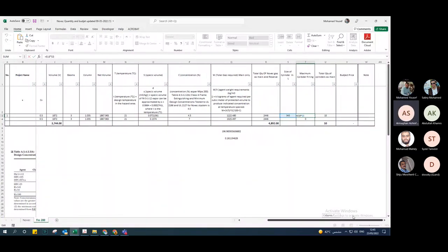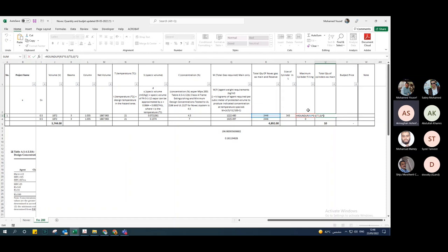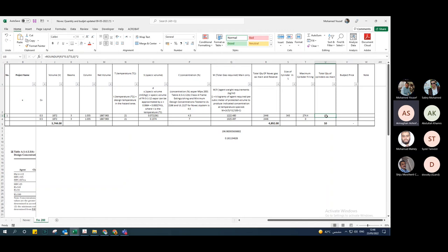I consider the cylinder to be filled to 80% of total capacity. I divide the total gas quantity by the maximum cylinder filling to get the number of cylinders needed. After that, I determine the header, piping network, and nozzles — which will be covered in another session.